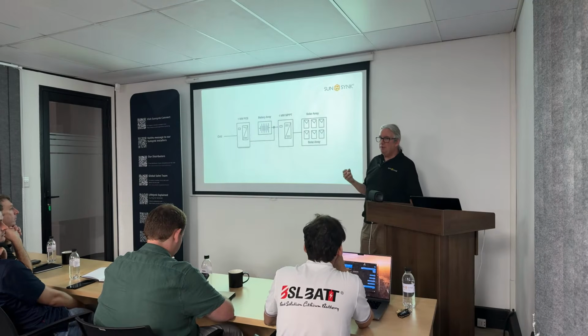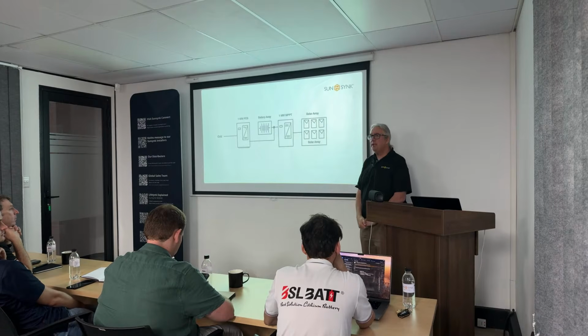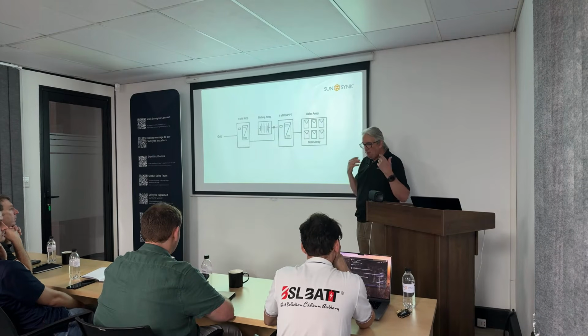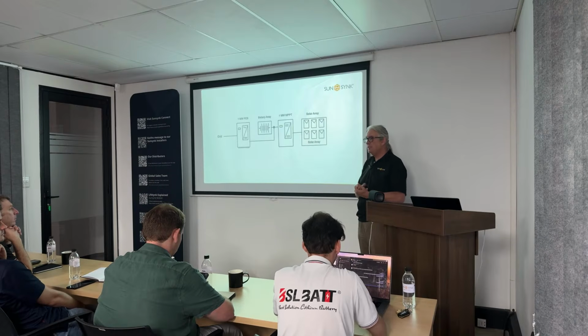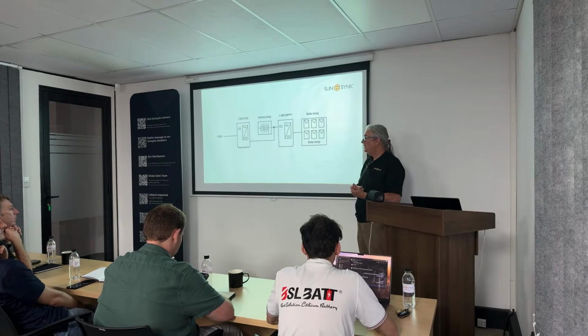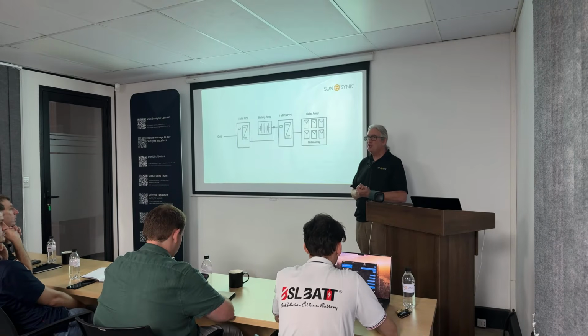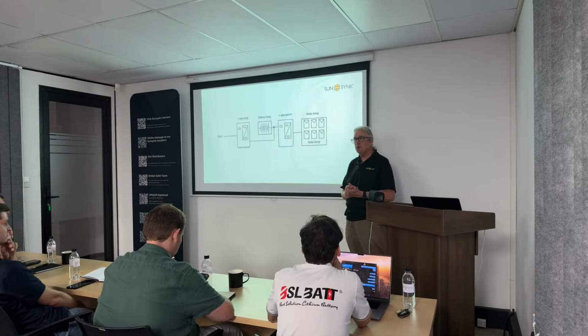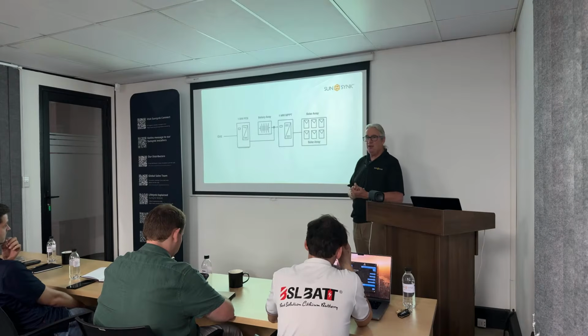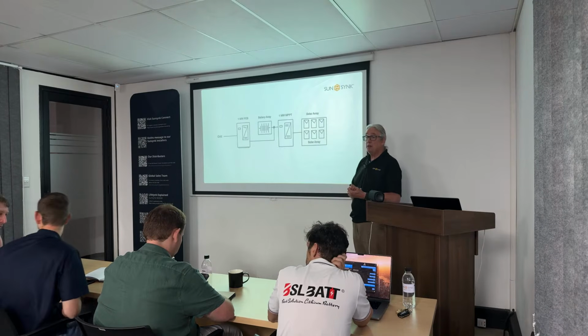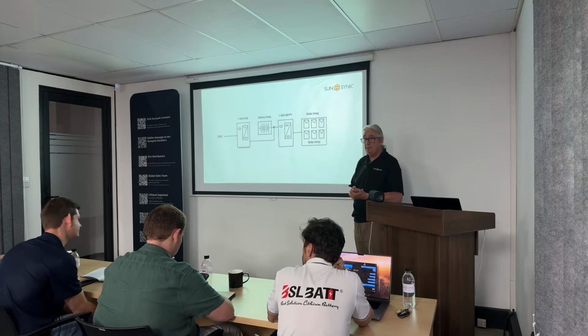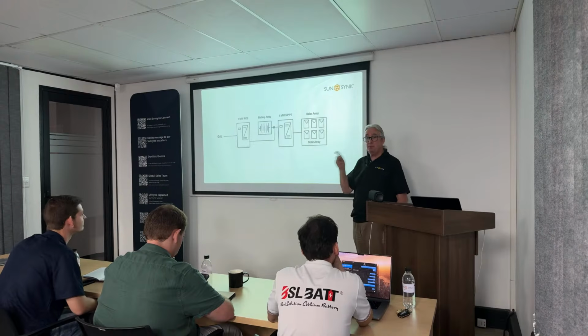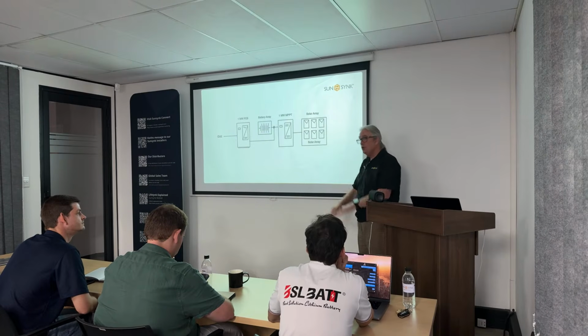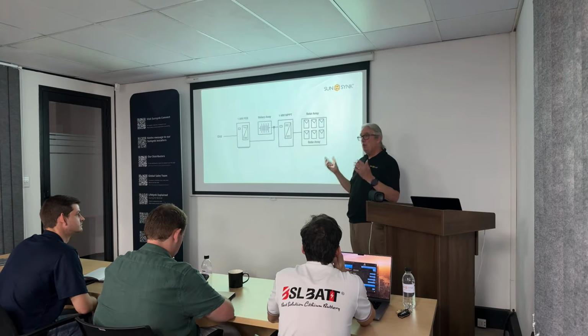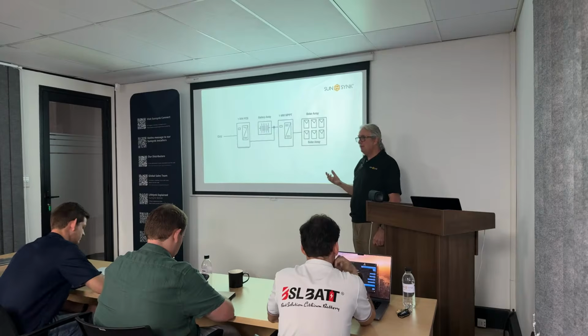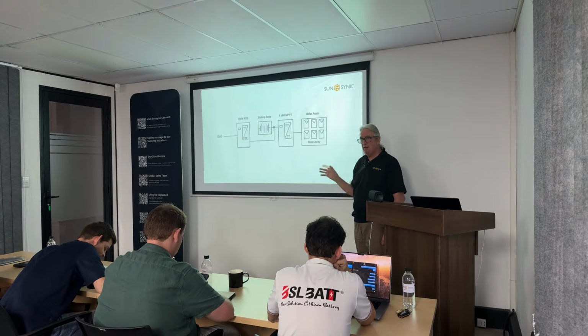Understanding the PCS, the power conversion, and the MPPT: the power conversion unit and the MPPT operate slightly differently. The MPPT has a boost converter. That means it doesn't have a buck, so the battery voltage is the highest point of the voltage. If the battery is 900 volts, the MPPT can't be higher than 900 volts. The reason for this ceiling is the battery level, and most similar systems on the market do the same. It can take a lower voltage, 400, and bring it up to the 900 volts of the battery, but if you went to 1,000 volts, it can't go down. But in South Africa you have a 1,000 volt limit, so you're fine.